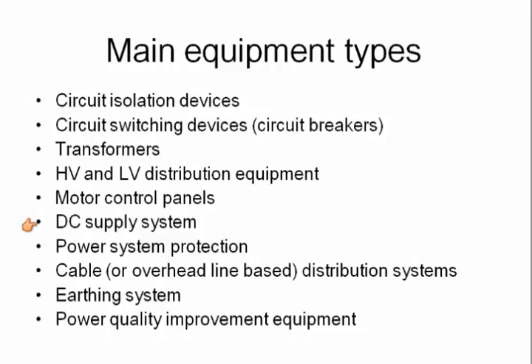You can run it with AC as well. However, the downside with AC, if AC supply fails, these things may not be functional. By having it on a battery bank, UPS, battery charger arrangement, you are ensuring that even if AC supply fails, power to your control and protection systems is functional. You have your relays, cable or overhead line-based distribution, earthing system, power quality improvement equipment. For example, your capacitor banks to improve the power factor.